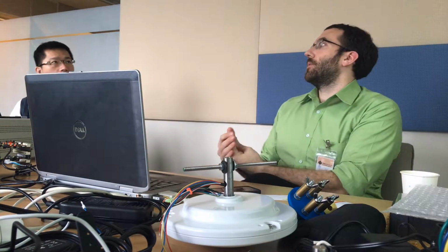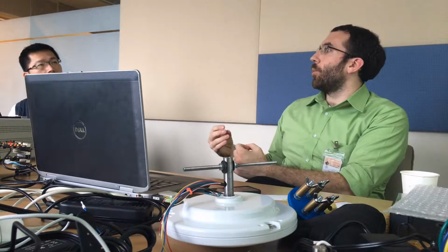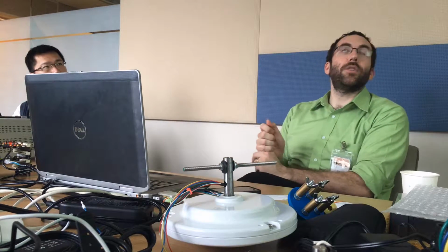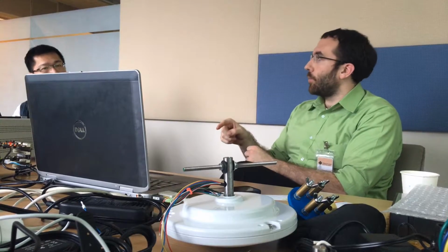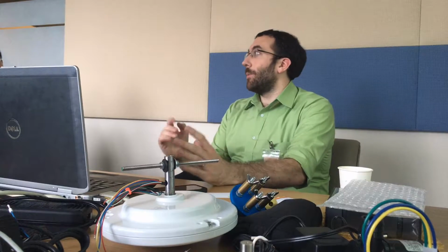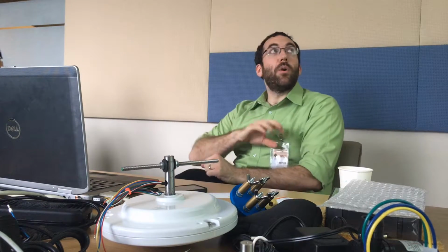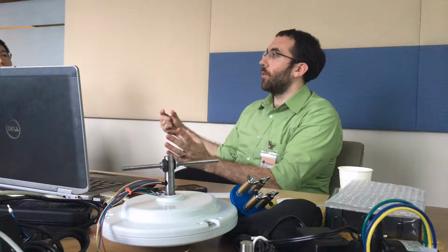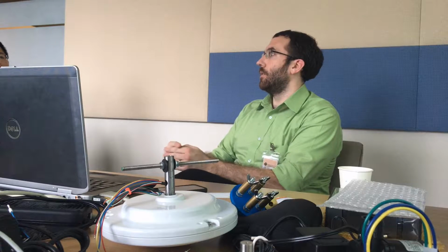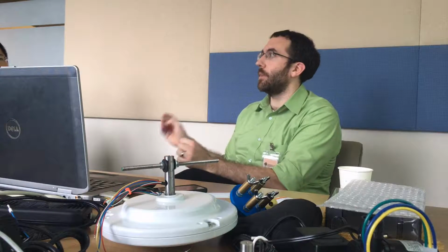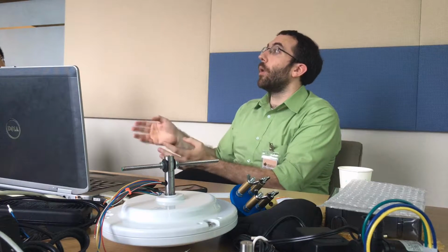Inside of KMS, we have scripts, and these automate a lot of the work for the customer. There are 4 key scripts within KMS. The first one is the parameter identification. When you click the identify parameters button, it goes out and runs this script. The important thing to note is that when you click that button, it will overwrite all of the settings you have, because it assumes that you've disconnected your old motor and plugged in a brand new motor. It does not assume you want to retain any setting. It will erase all of them and set them back to the defaults. So it's something to be aware of with a customer.